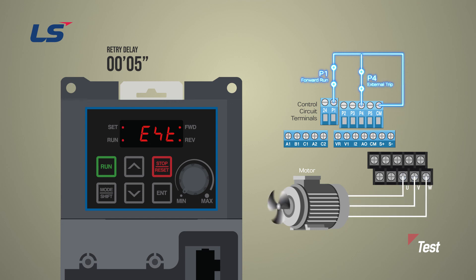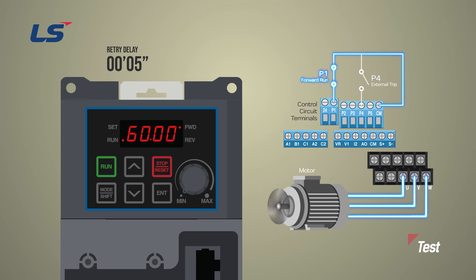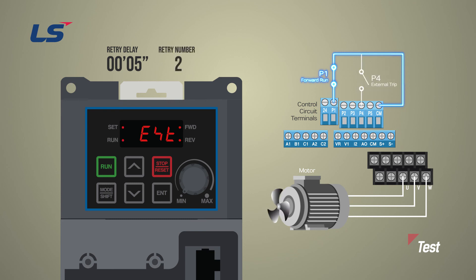Repeat several times in the same way. Since the number of restarts was previously set to 2, it can be seen that when the third external trip occurs, it does not restart even if P4 terminal is turned off. We have learned how to use the Reset-Restart function. Thank you.